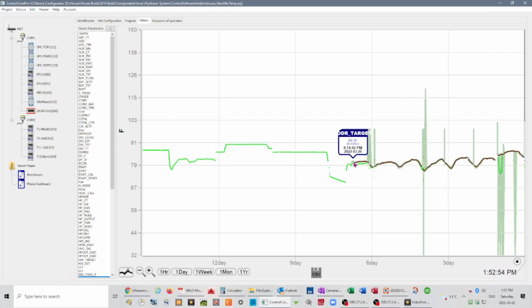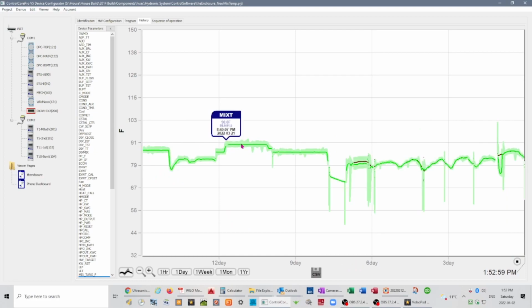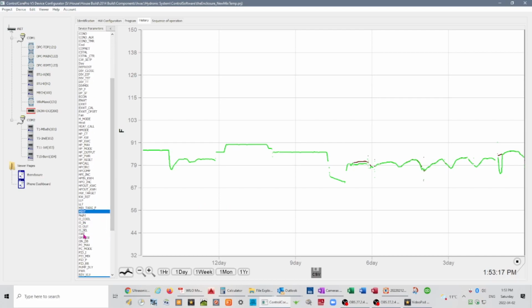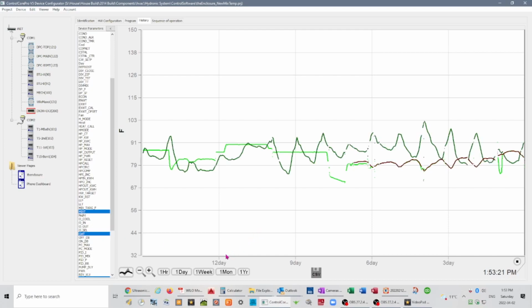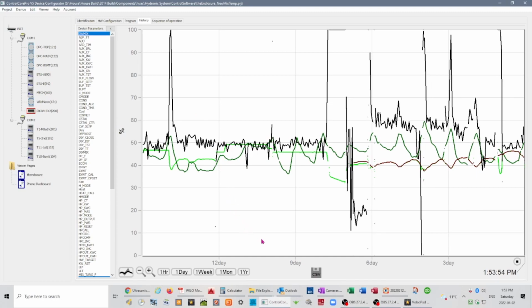Now it was back on the 26th that I rewrote the program. Prior to that, you can see how the mix temperature is very, I would call it linear. It has a lot of flat areas where it's not really responding to the outside temperatures like it is now. And if we put outside temperatures back on, you can see that now it's basically a mirror image of the outside temperatures, where before it really wasn't responding quickly enough to the outside temperatures, and it was just giving us sort of directional changes en masse as opposed to minuscule changes.